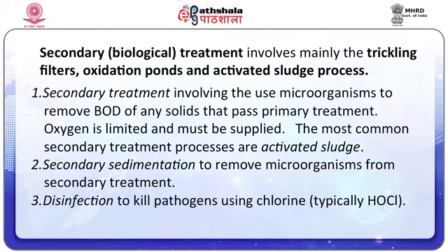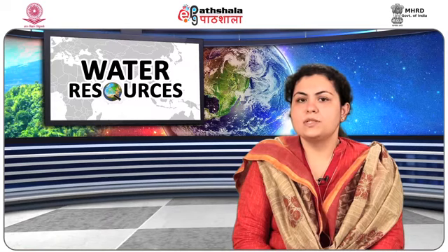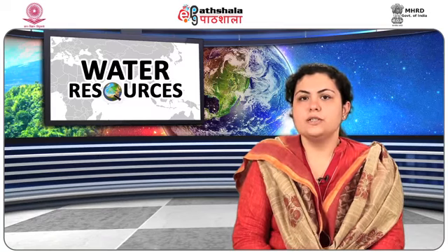Second, secondary sedimentation to remove microorganisms from secondary treatment. Third, disinfection to kill pathogens using chlorine. Purification by treatment on trickling filters depends primarily on absorption as well as adsorption of both soluble and suspended matter from the waste matter into and onto zoogleal slimes.